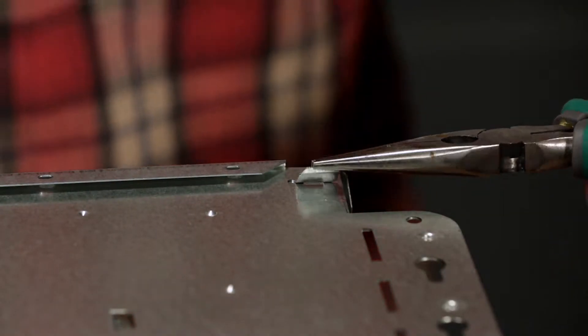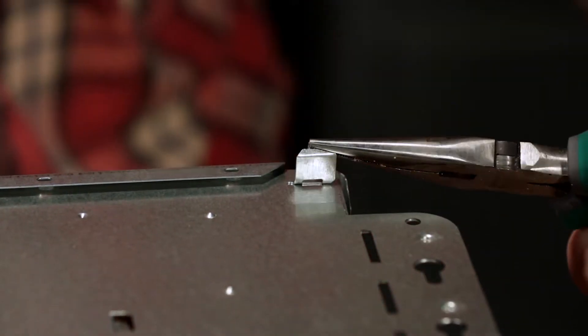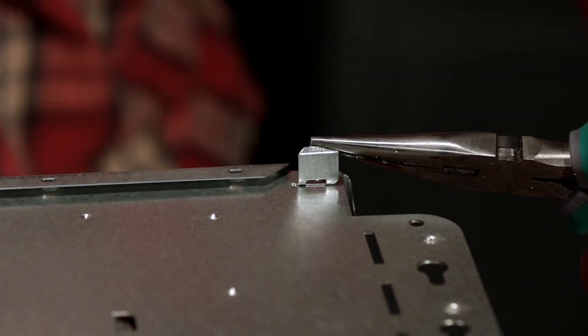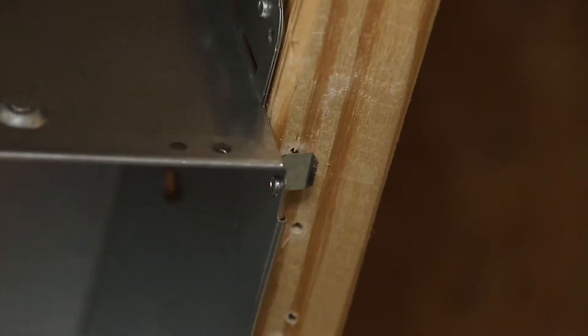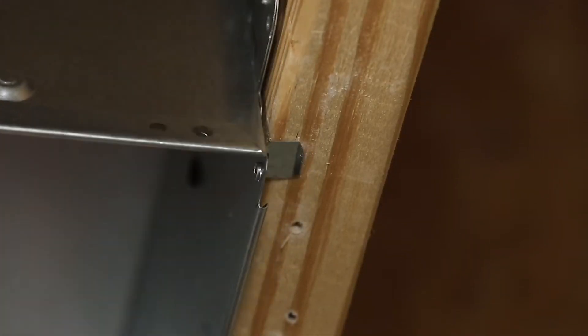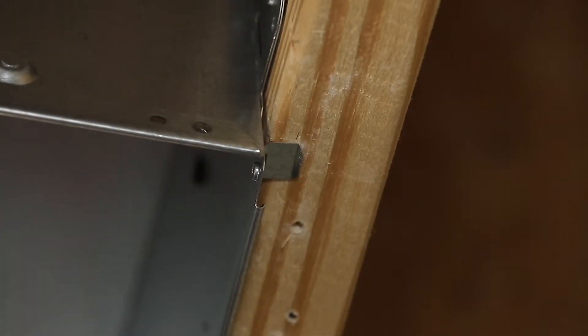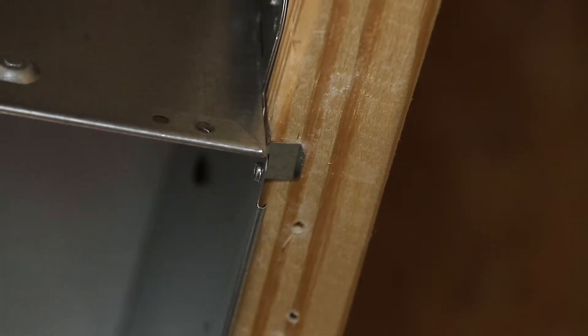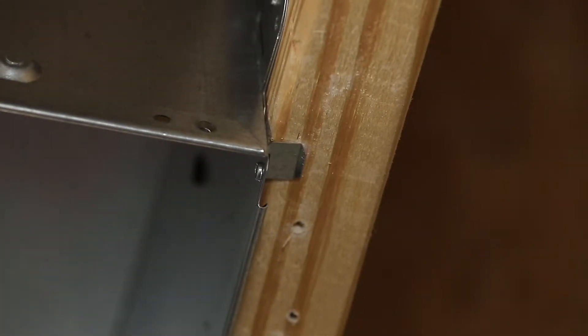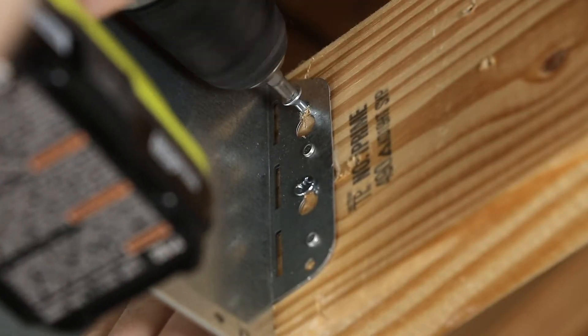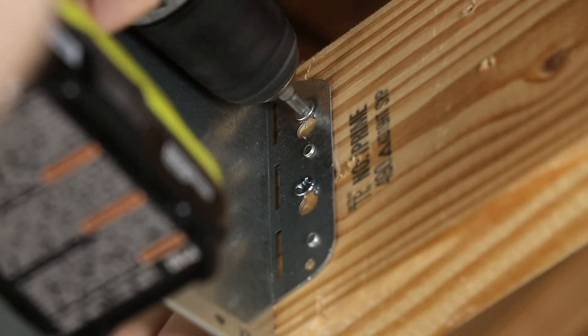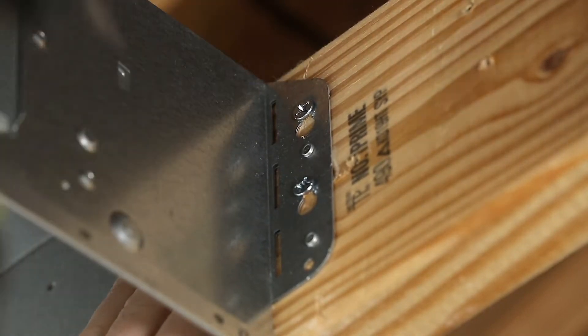When mounting the housing to the ceiling structure, ensure that the bottom of the housing will be flush with the finished ceiling. Bend out the housing tabs to fit against the bottom of the structure. Secure the housing through the mounting ears on each side with appropriate fasteners.